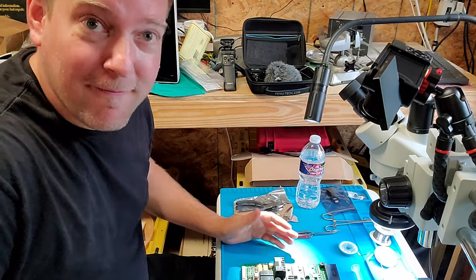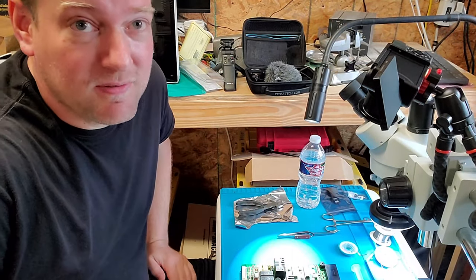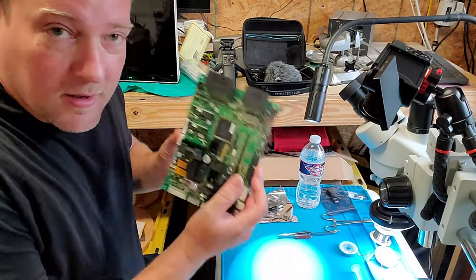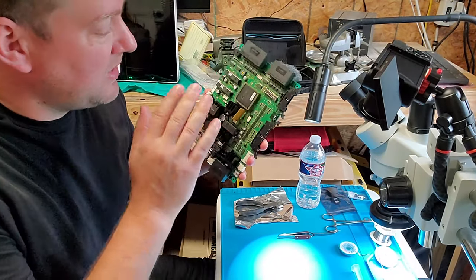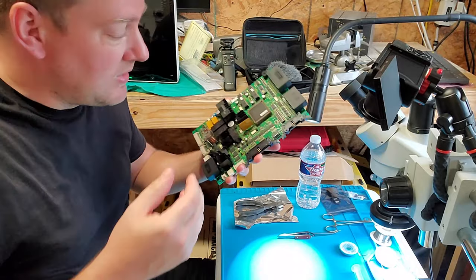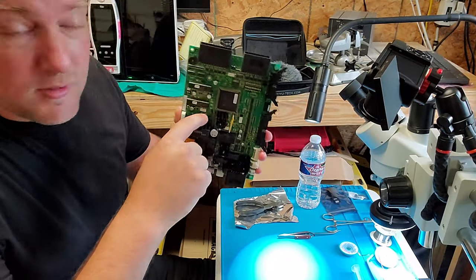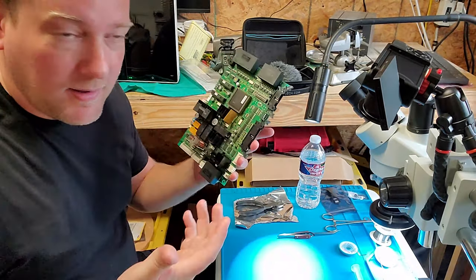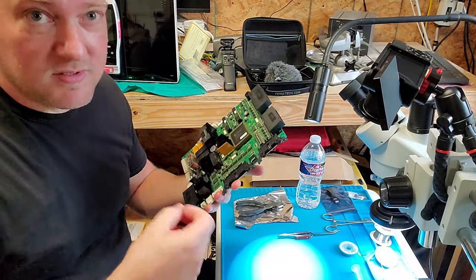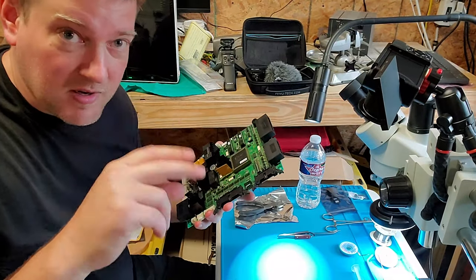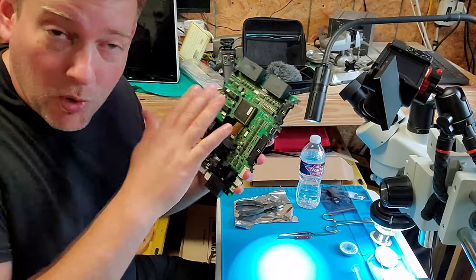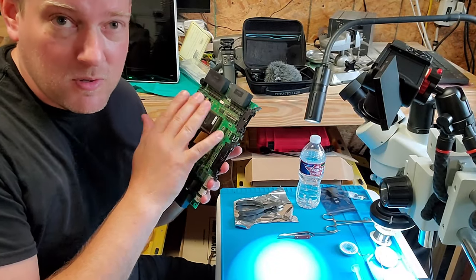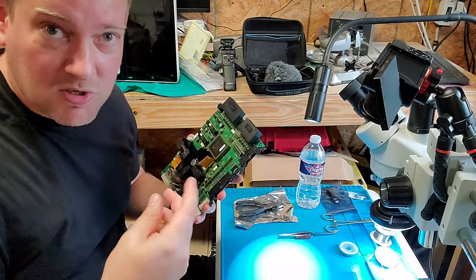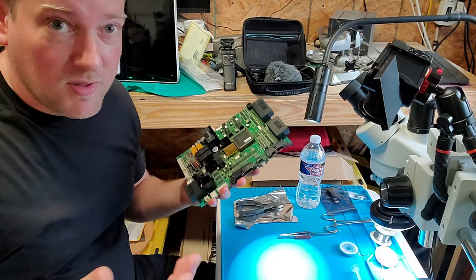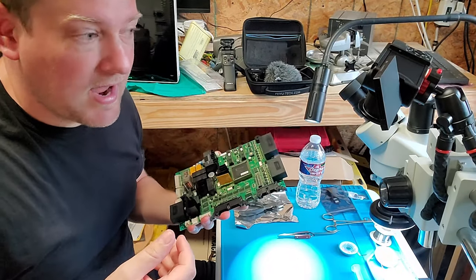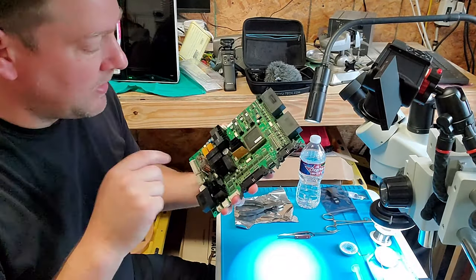Today I have finally received all the parts necessary to fix my board. This is the Skytron surgical table relay board to which the fuse is popped. I went over that in another video because the remote had some yanked cables which then had some conductors touching. The board pops a fuse, a microfuse, as a natural precaution to shut down parts of the table so that you can't inadvertently activate something that you don't intend to.